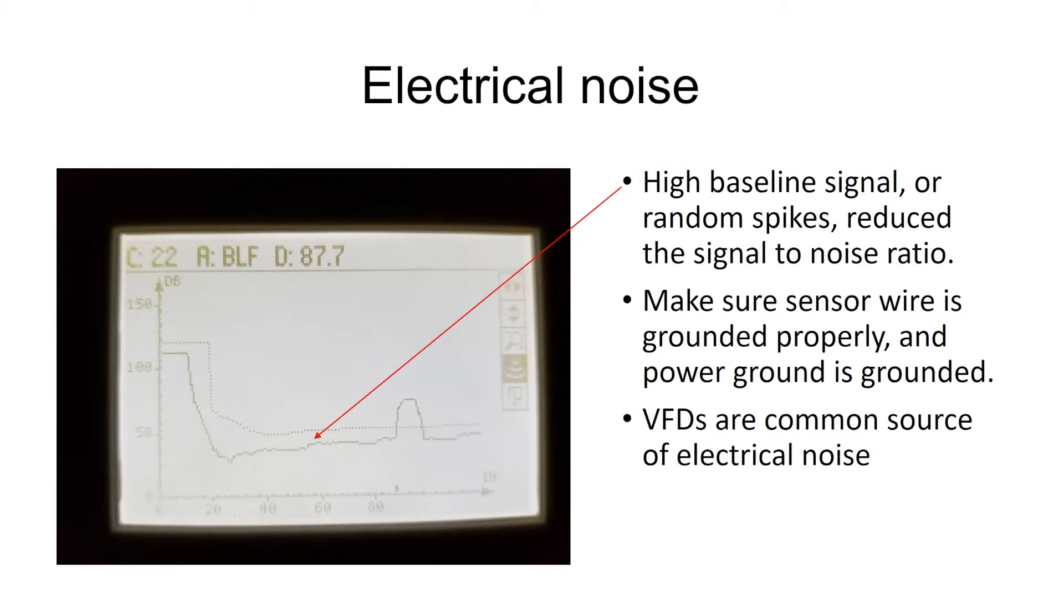Electrical noise can cause us a lot of problems also, especially if the signal wire we have coming from the sensor back to the level control is not grounded or not grounded properly. The two conductors in the shield that come from the sensor back into level control, I want to make sure that that shield is tied to the shield connection and also, I want to make sure that the power ground is tied to a good earth ground. What we're seeing a lot now is VFDs are just creating a tremendous amount of ambient electrical noise that can be picked up by the sensor.